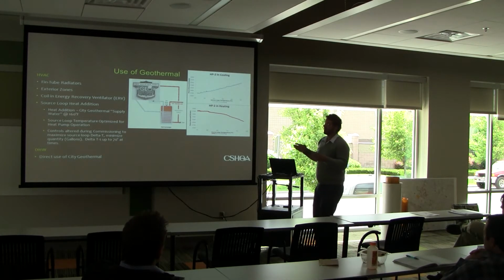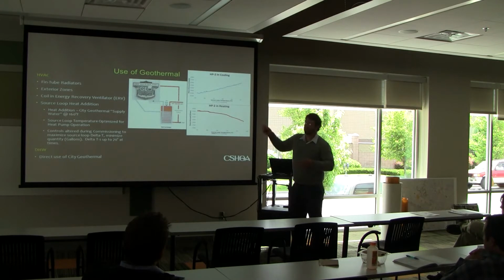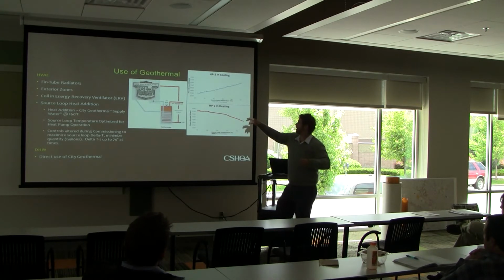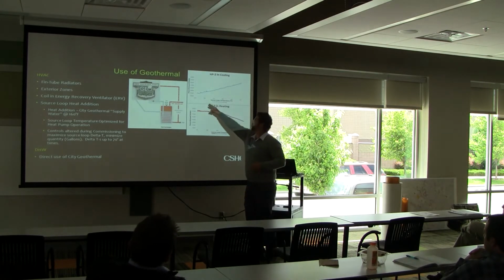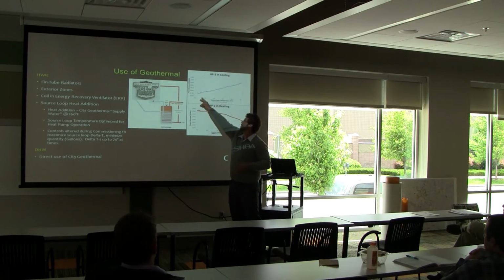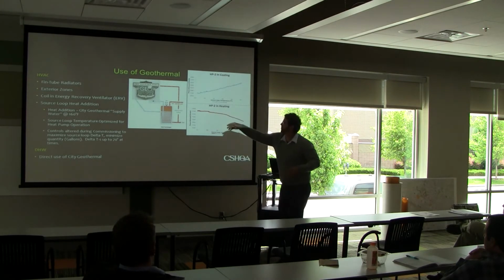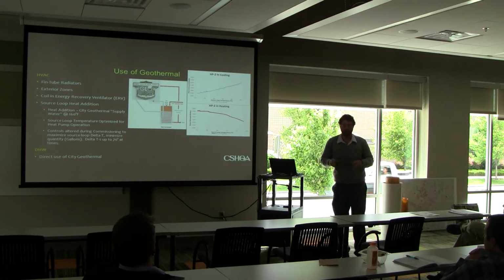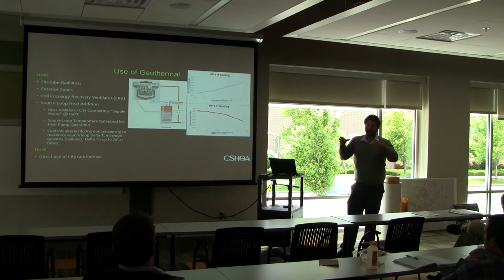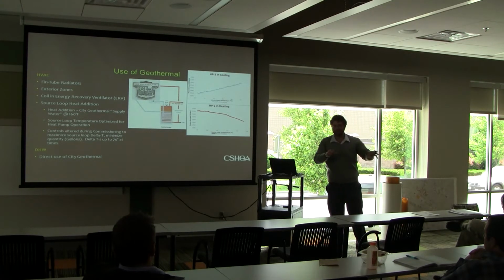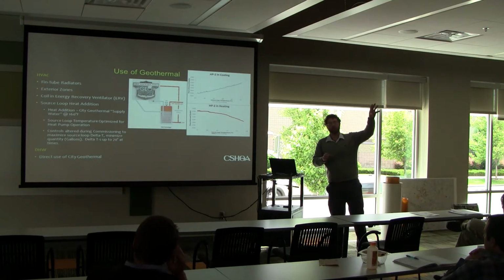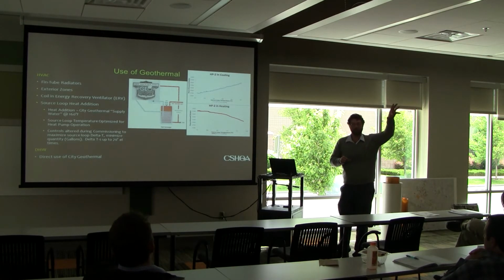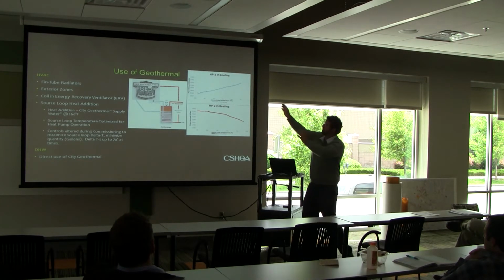So during the summer, when we're trying to reject a bunch of heat from the building itself, we actually run as cold a temperature as we can on that source loop, which ends up being a little bit below 69 at times. It depends on another efficiency point, which has nothing to do with this conversation, but the cooling tower itself has its sweet spot as well. So that was an optimization that we found.